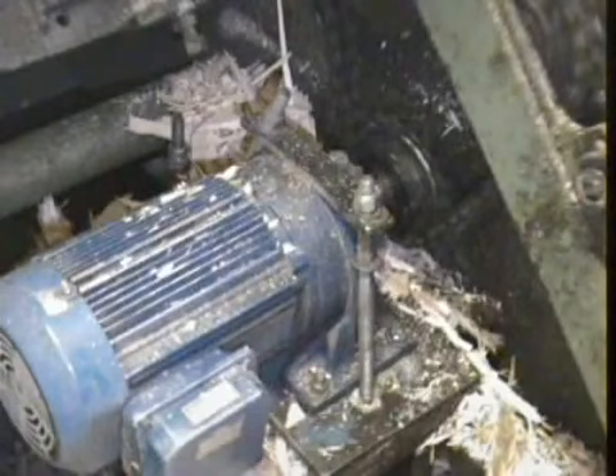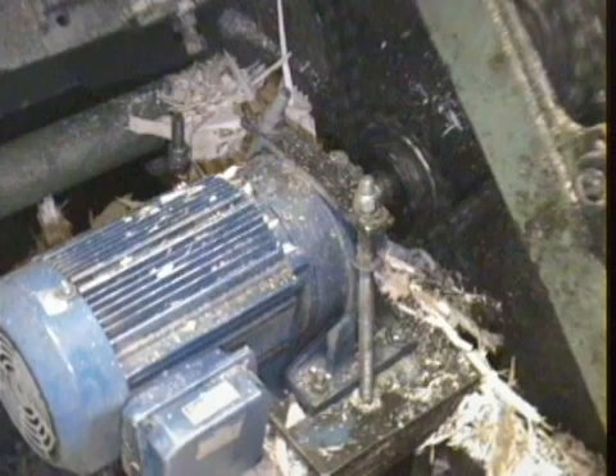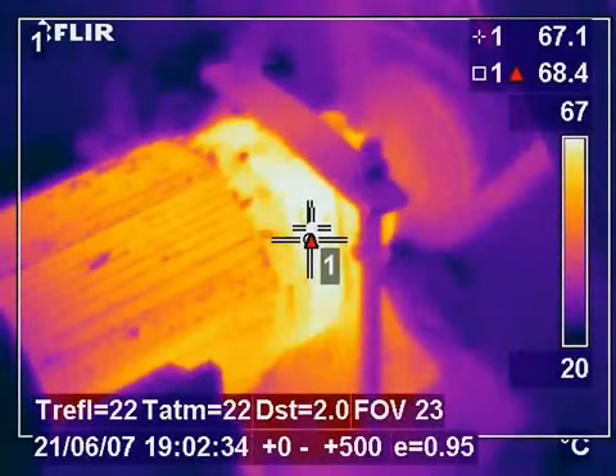A plant operator alerted us to a possible fault on a machine in a timber sawmills when he noticed an increased noise from the machine. The thermal image found that one of the motors on the machine had a failure on the front bearing. This caused an increased temperature and risked a possible fire, and in a timber sawmill this could be devastating.